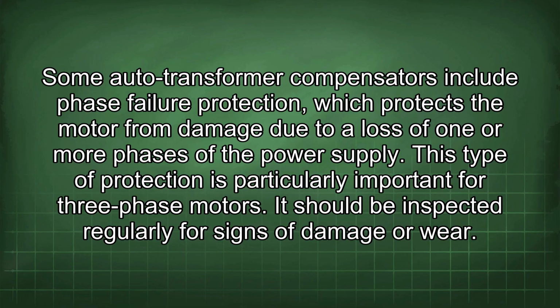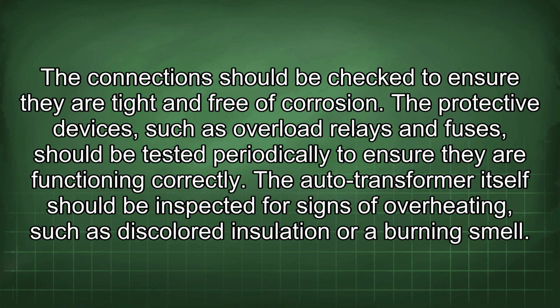It should be inspected regularly for signs of damage or wear. The connections should be checked to ensure they are tight and free of corrosion. The protective devices, such as overload relays and fuses, should be tested periodically to ensure they are functioning correctly. The auto transformer itself should be inspected for signs of overheating, such as discolored insulation or a burning smell.